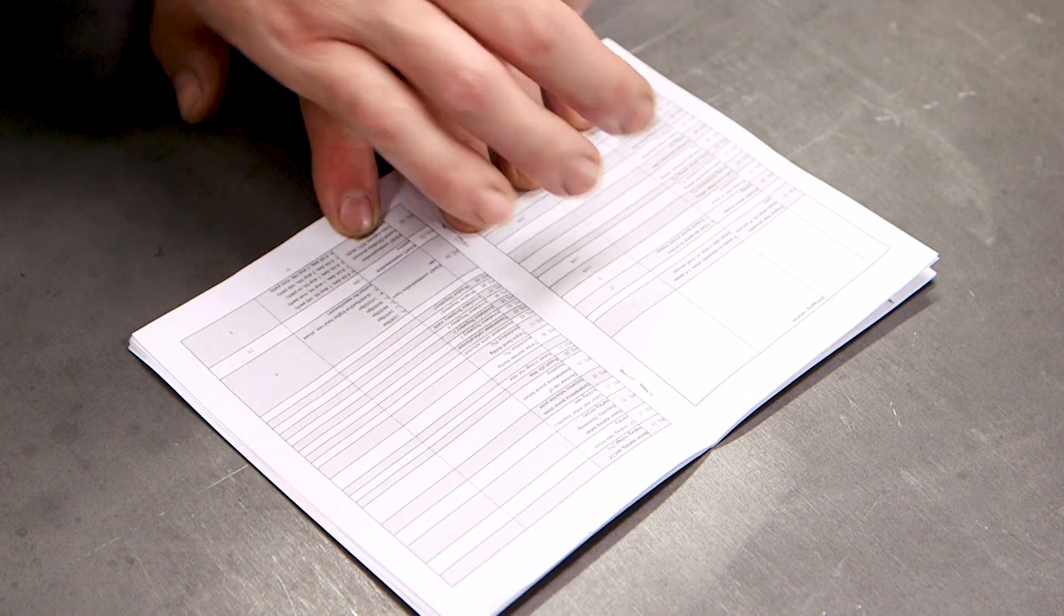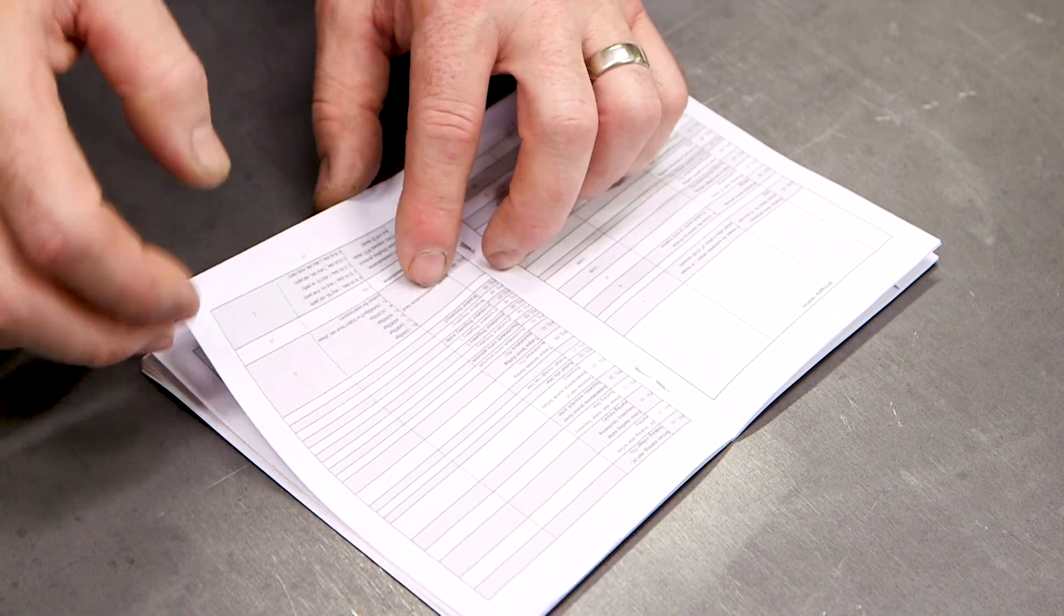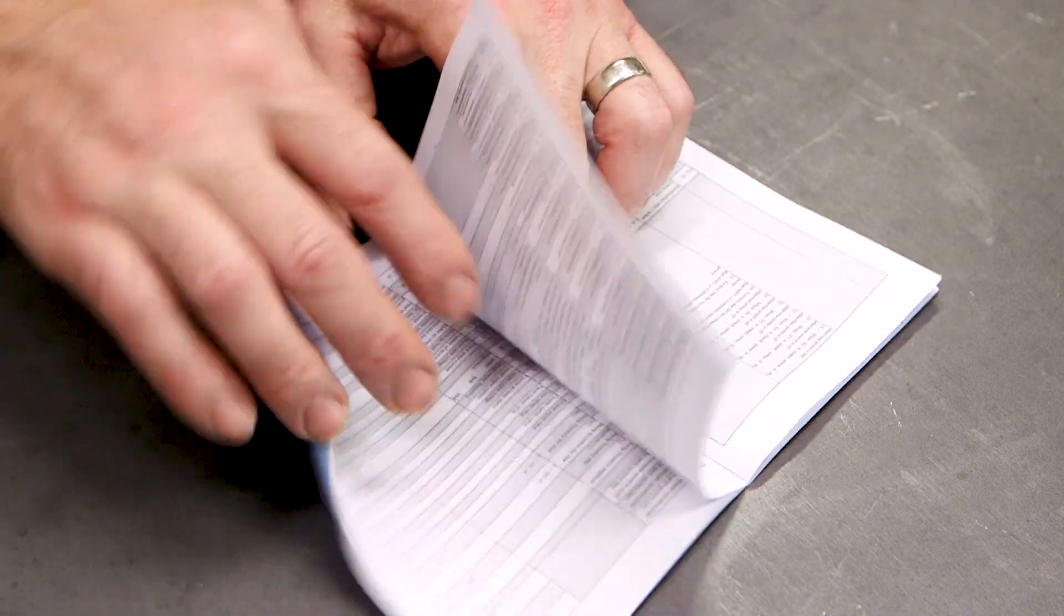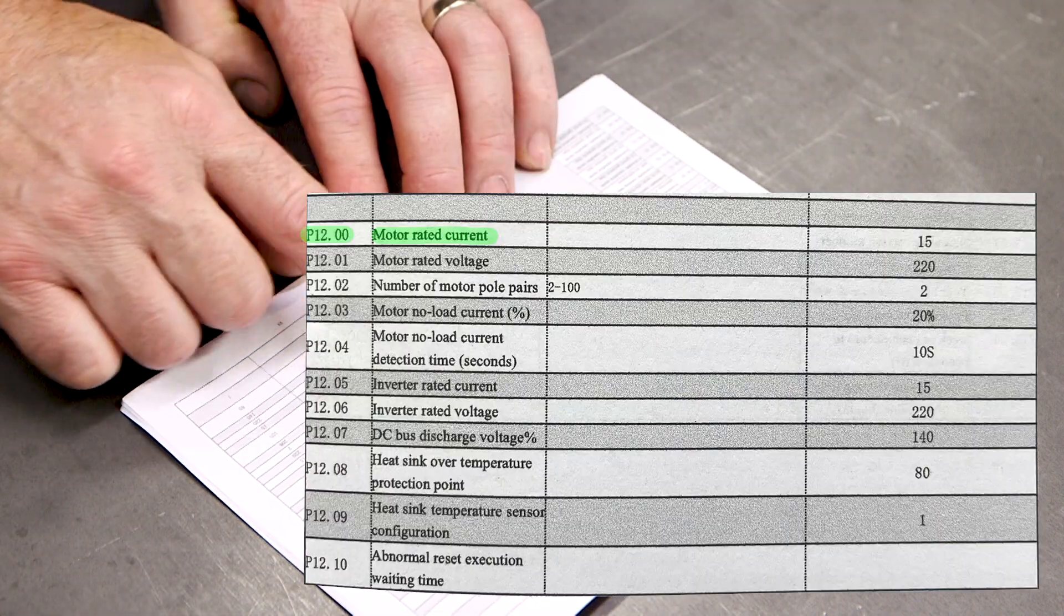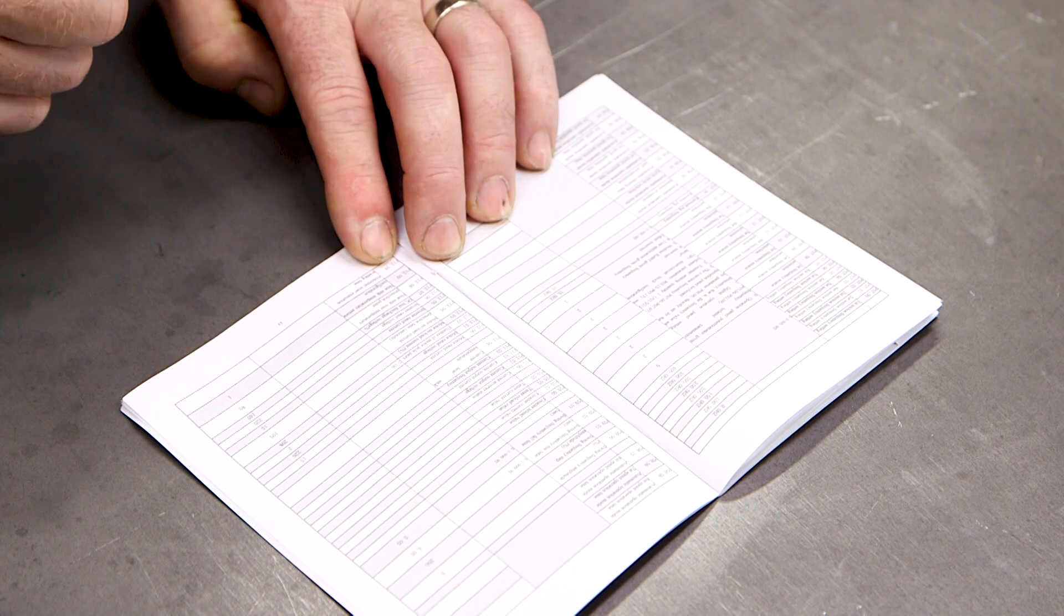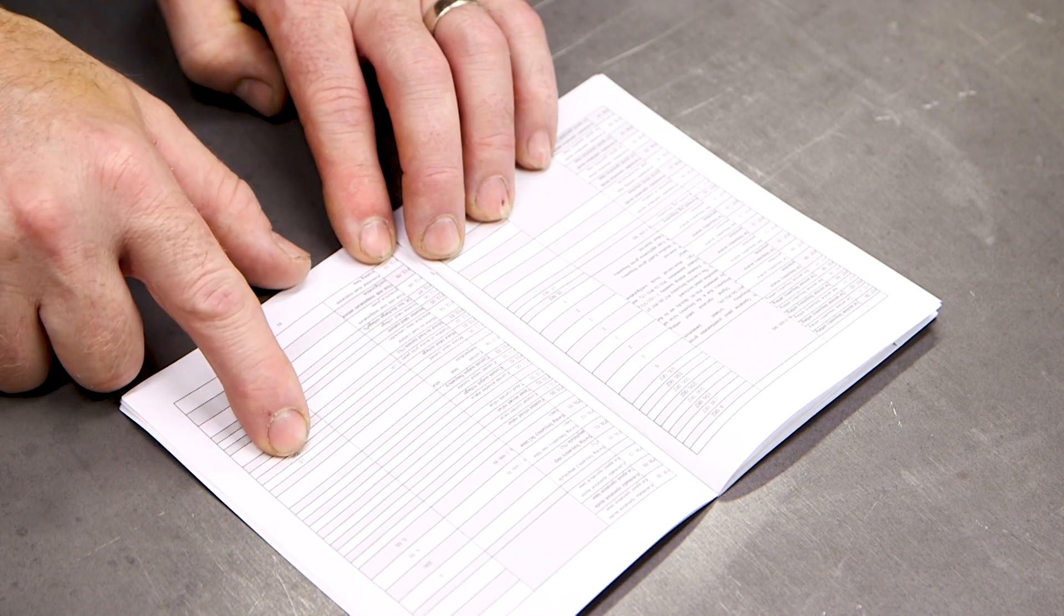One thing they don't mention in that simple startup table is the actual motor configuration. And on this VFD, that's in the 12 series parameter codes. So P1200, that's the motor rated current. This is set at 15. I pulled that off the nameplate of my motor. It was only 2.8.